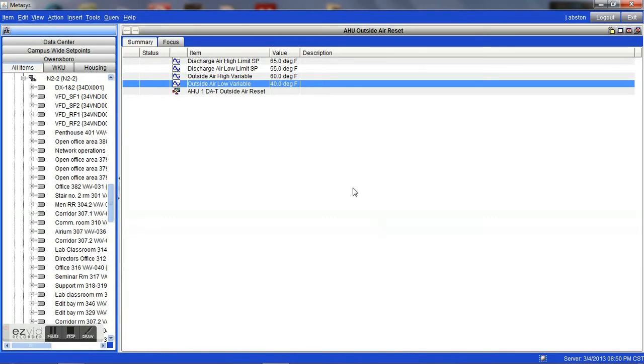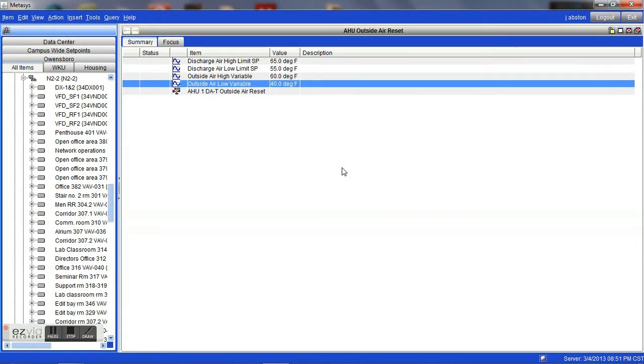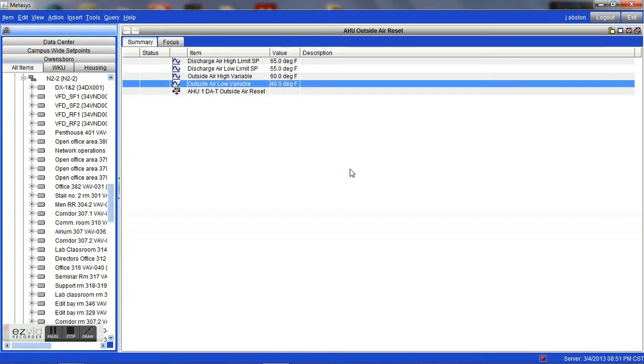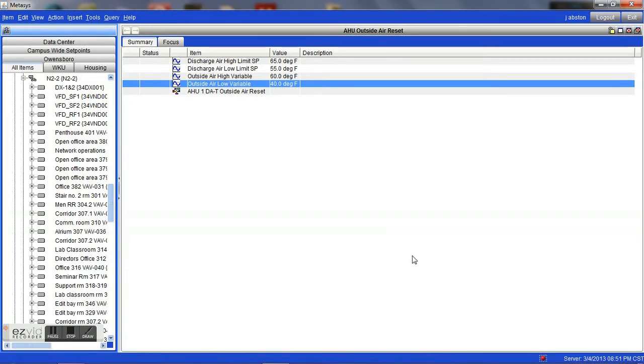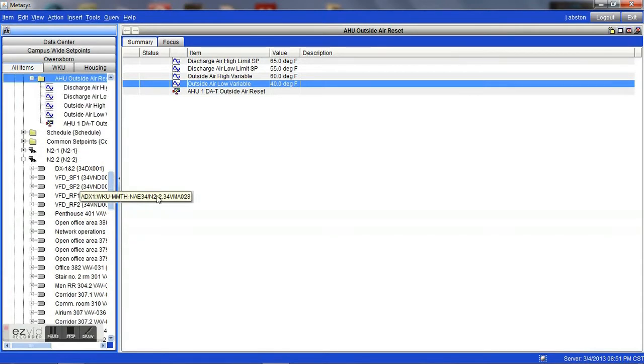If you have a 55 degree discharge temperature from an air handler and a reheat valve is having to stay at 100% all the time to maintain a 72 degree room temperature, by raising that temperature from the air handler, you can greatly reduce the amount of hot water or other type of energy used to reheat that air. There are just some basic elements that can be done in your program logic. Each energy management system is a little different. However, there are some basic principles that will apply to all.